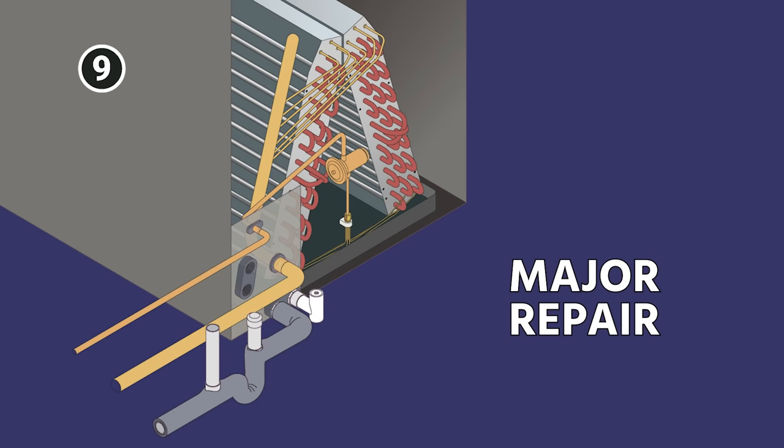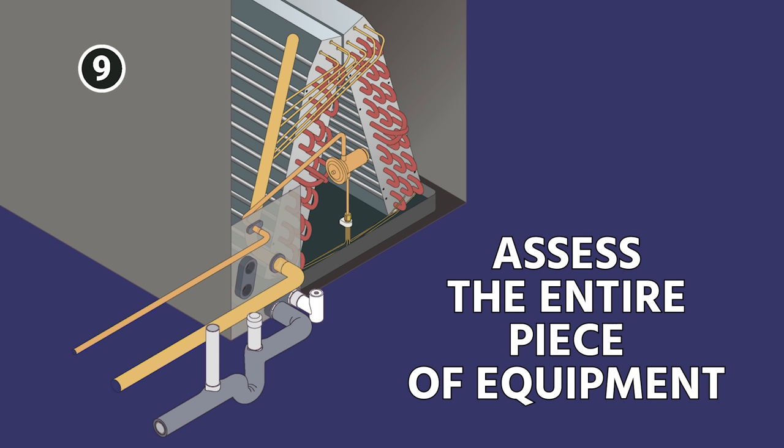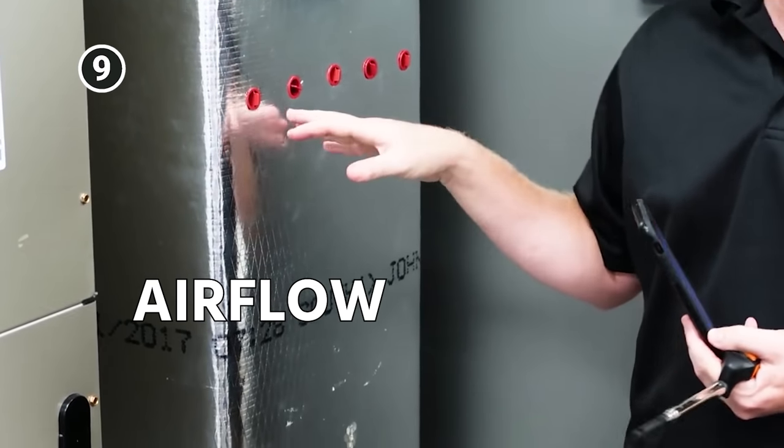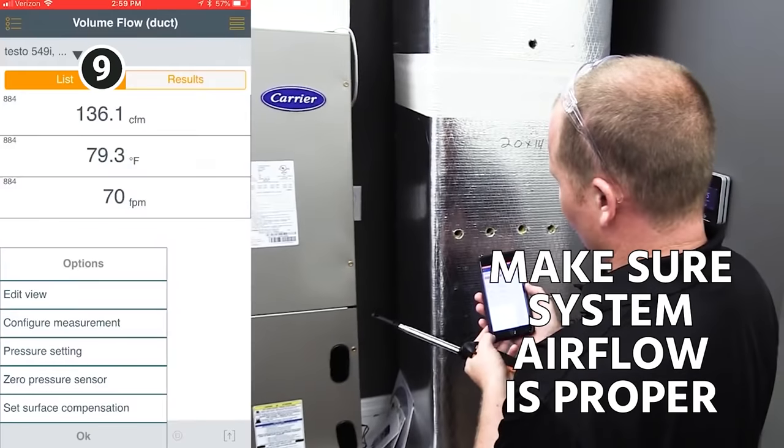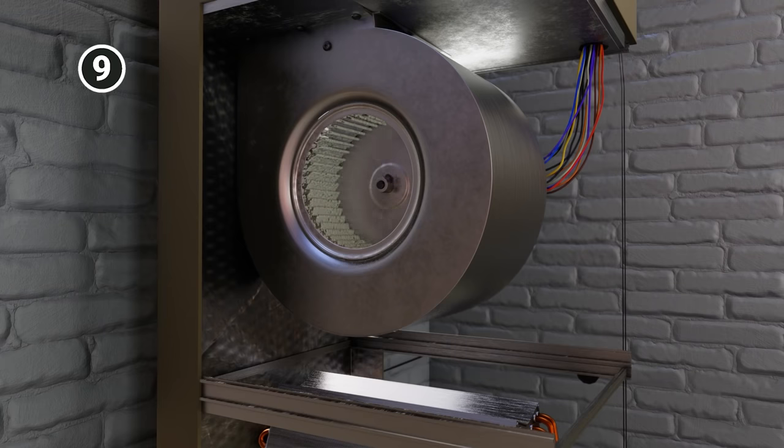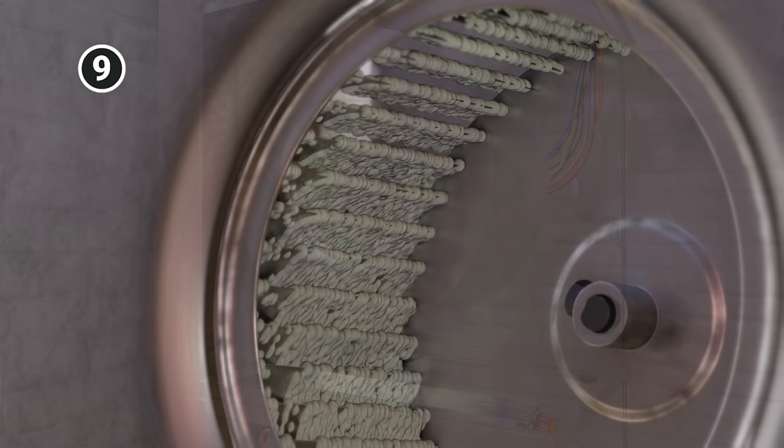Because again, when you do a major repair like an evaporator coil, presumably you replaced it because it was leaking, you have to assess the entire piece of equipment. And one of the most overlooked things is airflow. Make sure that the system airflow is proper. At the very least, make sure to do a solid visual inspection on everything else. Things like your blower wheel, as an example.